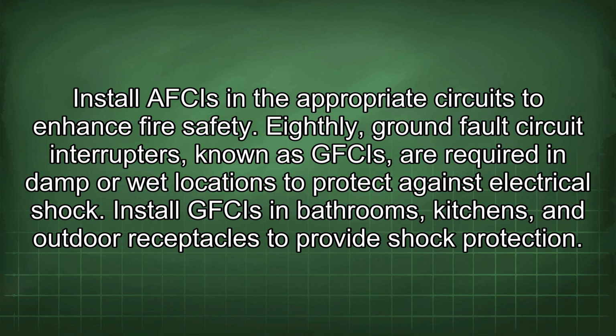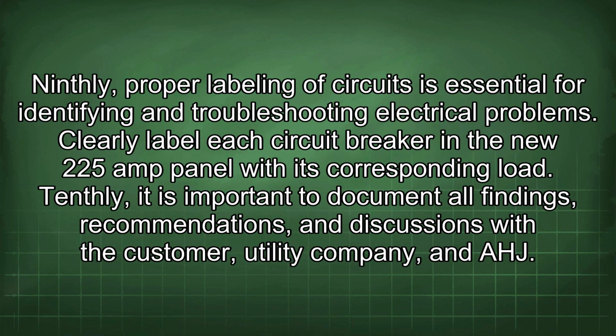Install GFCIs in bathrooms, kitchens, and outdoor receptacles to provide shock protection. Ninthly, proper labeling of circuits is essential for identifying and troubleshooting electrical problems. Clearly label each circuit breaker in the new 225 amp panel with its corresponding load. Tenthly, it is important to document all findings, recommendations, and discussions with the customer, utility company, and AHJ.